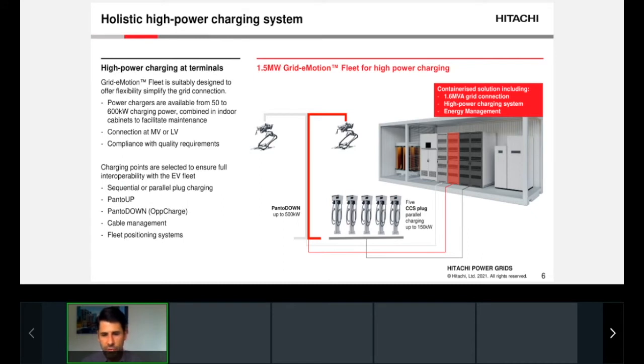Looking at the overall system, we have our rectifier transformer, rectifier, and DC-DC converter - all modules we can combine and recombine to tailor the overall system to the fleet and operational requirements. We can create lineups ranging up to 3 megawatts in total system size, and combine different charging interfaces, from the pantograph to simpler cable-based solutions.